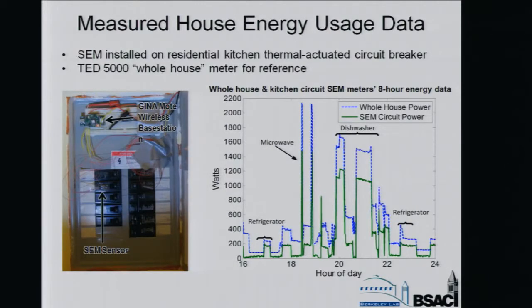We also installed this system in a residential building to verify its real-world performance. What we did is we installed our sensor on a residential dwelling on the kitchen circuit. This panel also had a TED 5000 whole panel meter installed, which served as the reference meter for our measurement. The way we calculated the K factor for calibration is we plugged in various resistive loads to outlets in the kitchen, and we monitored the change in the output of our SEM sensor, and then we were able to correlate our sensor's output to real power in watts.